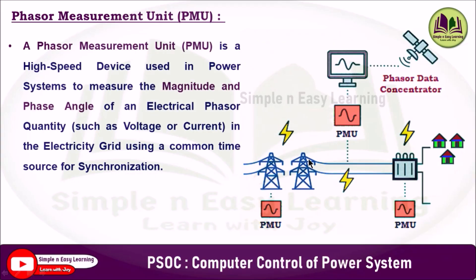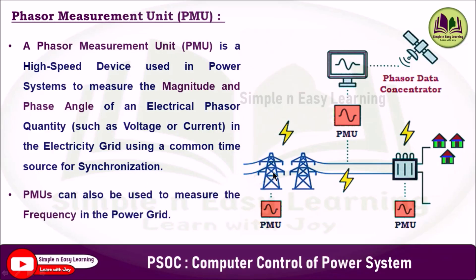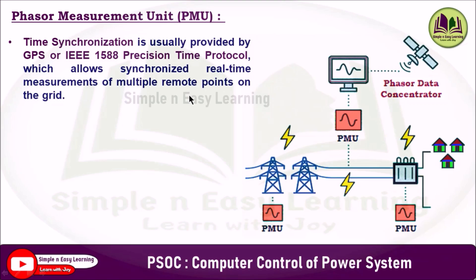The phasor measurement unit is a high-speed device used in power systems to measure the magnitude and phase angle of electrical phasor quantities such as voltage and current in a power grid, using a common time source for synchronization. Phasor measurement units can also be used to measure the frequency in the power grid. Time synchronization is usually provided by GPS — global positioning system — or IEEE 1588 Precision Time Protocol, referred to as PTP.